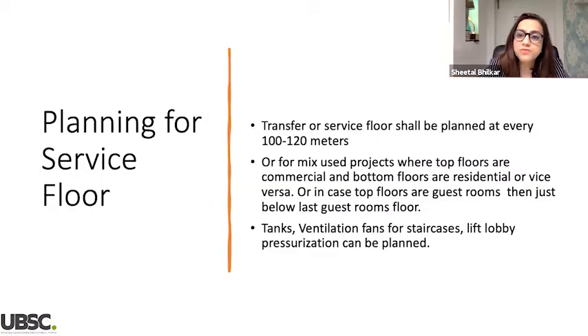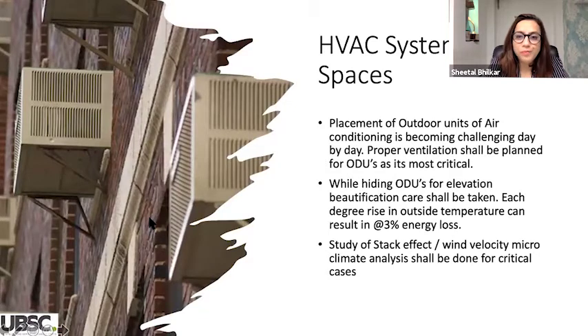A service floor is very important and should be planned at every 100 to 120 meters. Also for mixed use projects, like sir had given as an example, where the top floors are commercial and bottom floors are residential, or vice versa, you will have to have a service floor in between to divert all the services. Even tanks, ventilation fans for staircases, and lift lobby pressurization can be planned there.